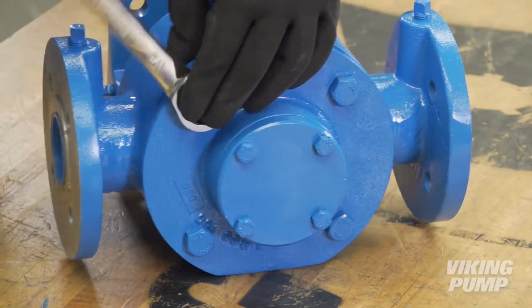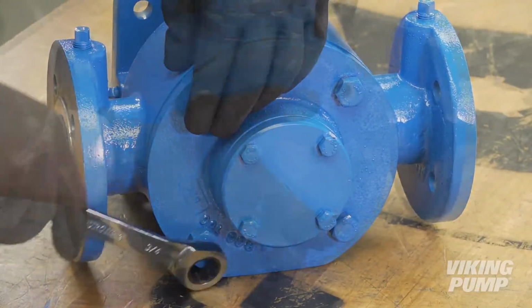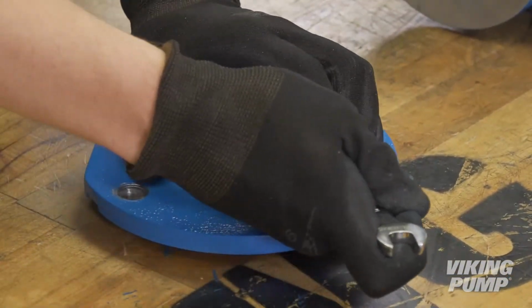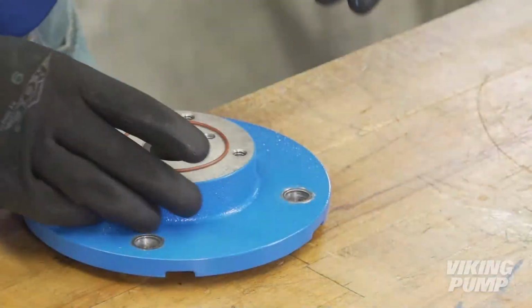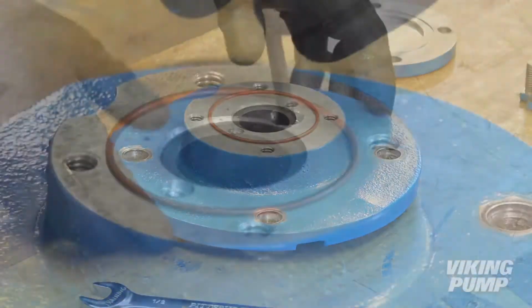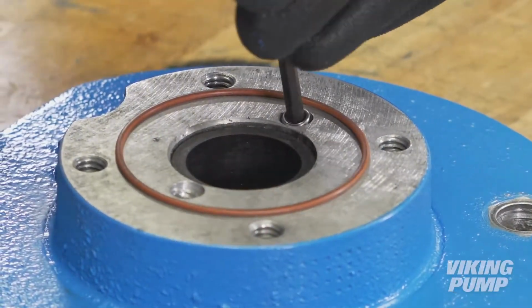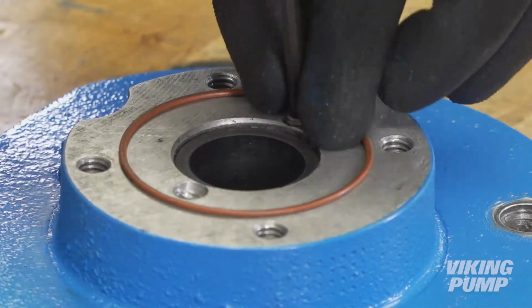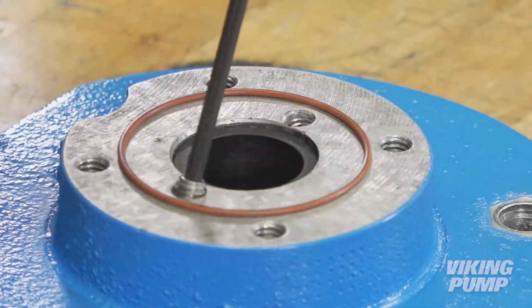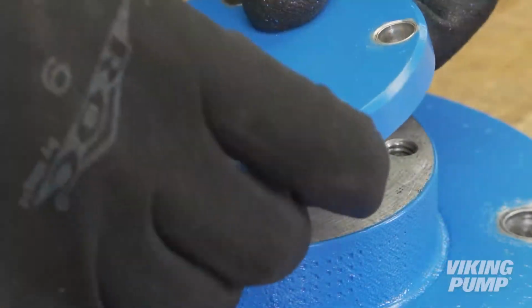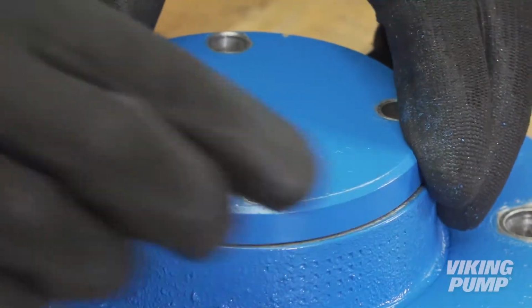Next, remove the pump head. Remove the end cap. Under the end cap, there are two internal flow paths. One of them is plugged. Remove the plug with an Allen wrench and reinstall in the other hole. You may now reinstall the end cap.